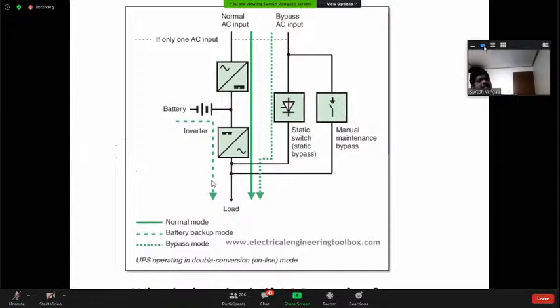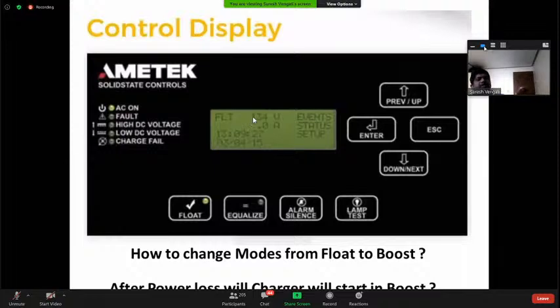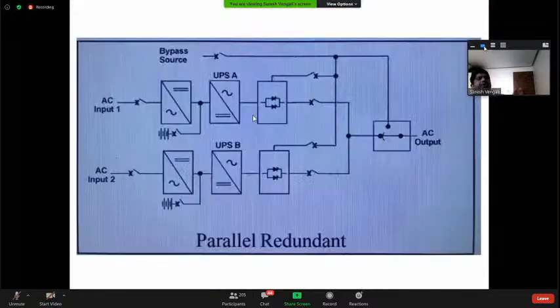After that, here I've seen a very interesting thing, this is a load. You may say 120 volts DC is required, or here you may say AC, like 125 AC. If you say 125 AC, you cannot get exactly the same, you may receive 130 volts, or 135 volts. So I will show you here: you see 134 volts, but actually your requirement is 120 volts. So where is the remaining voltage going, where is it dropping?